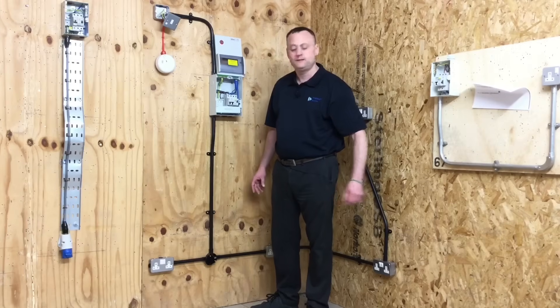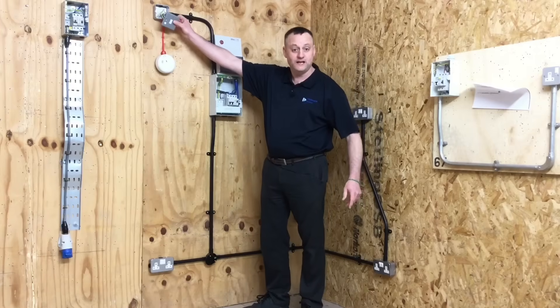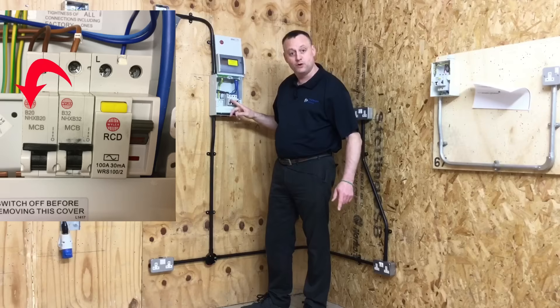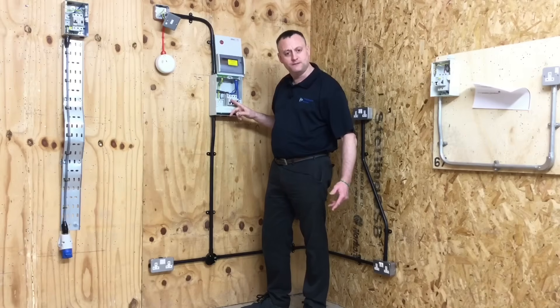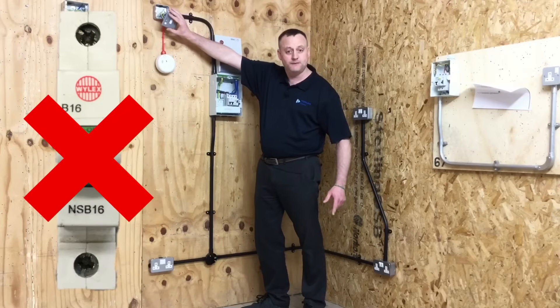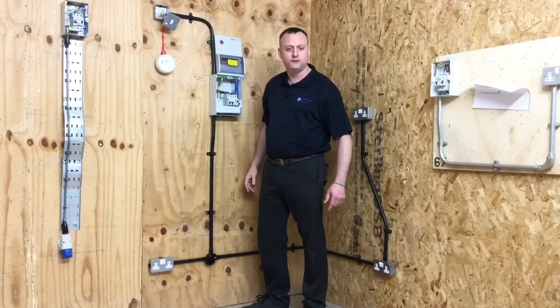We installed a radial circuit for the smoke detector from a fused connection unit, changing the fuse in it to a 3-amp fuse. We installed a 20-amp type B circuit breaker wired in 2.5 mm cable to feed the fused connection unit. We selected a 20-amp device because we wouldn't want to use a 16-amp device — if the FCU had a 13-amp fuse, we couldn't guarantee discrimination, a term that will be changed under the 18th edition to 'selectivity', between our overcurrent protection devices.